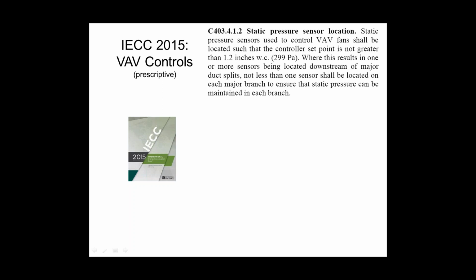All right, VAV controls. There's lots of rules for VAV controls. I'll try to highlight them for you guys that specify, buy, or install VAV systems. The first one, which is an interesting rule, is that we used to always locate the VAV static pressure sensor 2/3 down the duct. Why do we put it there? Because we've always put it there, right? No particular reason. We knew that we'd get a decent average down there, get it close to the control zone. In the perfect world, what we'd do is measure the pressure drop across the worst VAV box and we'd control down by that.